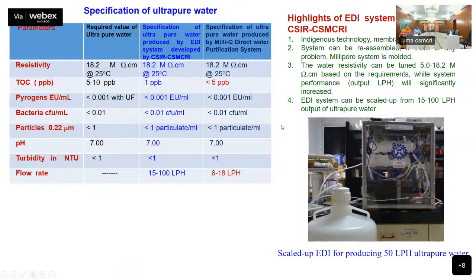The advantage of our unit is that with Millipore, once your cartridge is not working, we have to throw it away, but ours is a plate and frame model. So we only need to change the resin. And sometimes if the membrane is broken, then we need to replace the membrane, but the hardware component will remain the same.